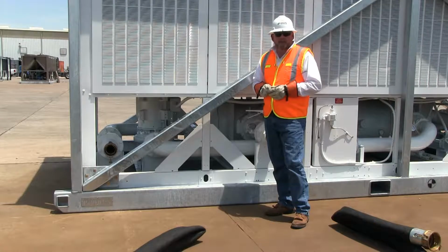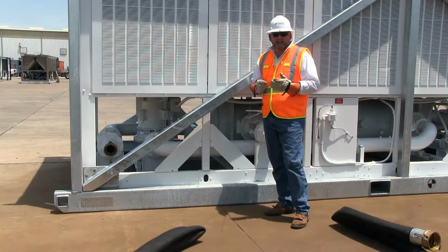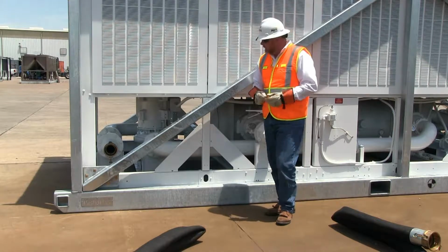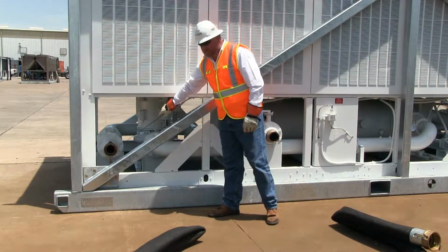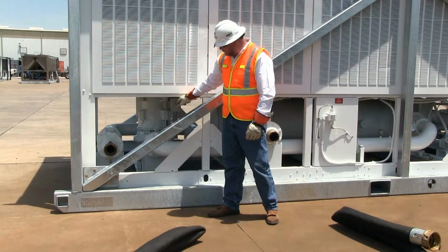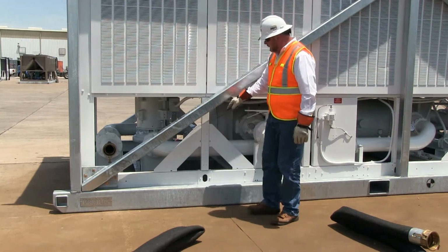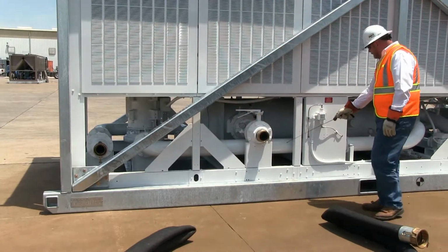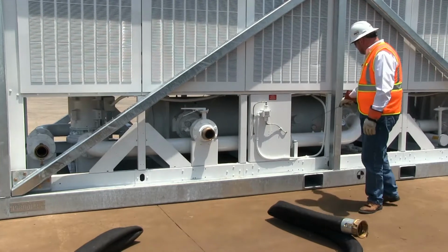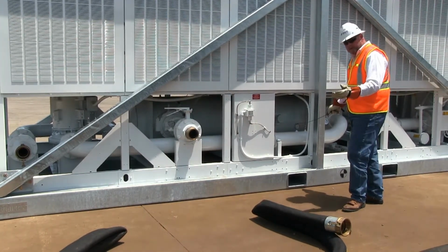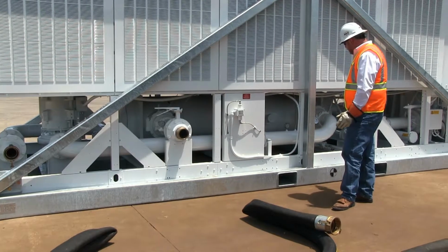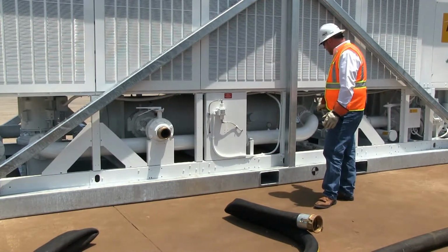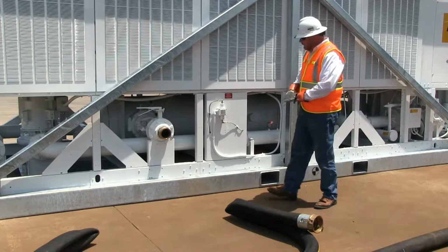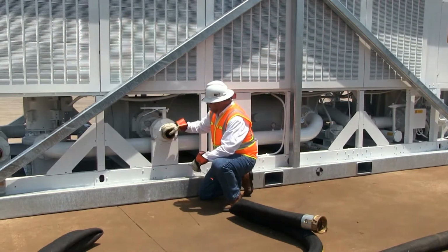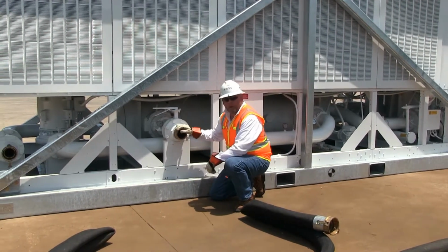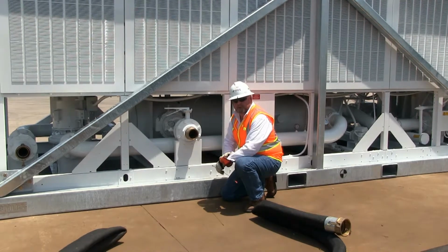Okay, now that we're getting ready to plumb the system, let's go over a little bit more of the connections and the gauges and instrumentation that we've built into the machine. First of all, the female 4-inch Camlock is the inlet, and that's our inlet into our pump or to our loop off our customer supply line. It's going to come off the pump and go through this pipe here through the heat exchanger. Over here, notice that we've got a compound gauge here to read our pressure, what's going into the heat exchanger. We also have a manual thermometer here as well and a test port. The water's going to go in through the heat exchanger, and this is our outlet here. Main outlet, it's got a male Camlock on this, so this is going to be our cold water going to our air handler or to our process chilling application.